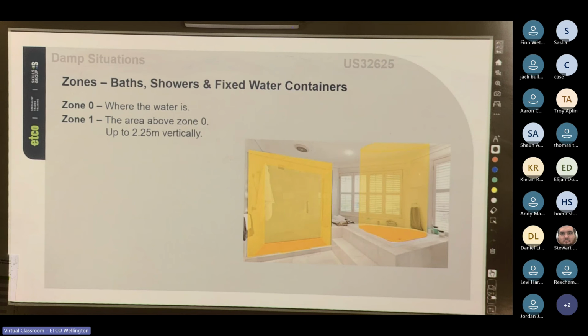Why 2.25 meters? Why do you think it's a height of 2.25 meters? Splash, yep. Ceiling height plays into it. Your standard ceiling in New Zealand is about 2.4 meters from the ground. Condensation. People height, yeah. So 2.25 meters is the safe out of touch distance. So it is a distance where it is considered safe from someone being able to reach it.